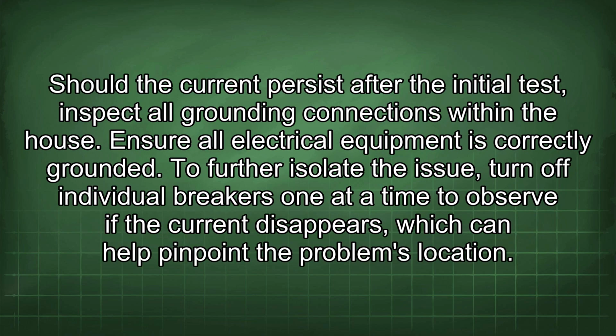Should the current persist after the initial test, inspect all grounding connections within the house. Ensure all electrical equipment is correctly grounded. To further isolate the issue, turn off individual breakers one at a time to observe if the current disappears, which can help pinpoint the problem's location.